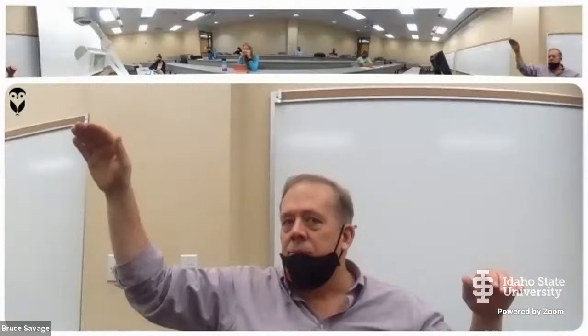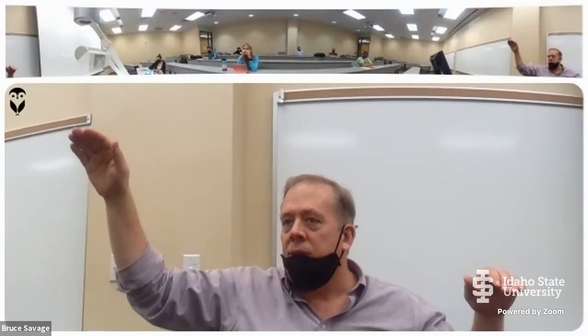So the question to the whole class, what happens if you have 100 feet of head and he puts in a pump that is designed to add 100 feet of head? That's the shutoff head. What happens then? Yeah, you may have a drop come out, or a drop go the other direction, but nothing. As soon as he puts in a pump with 101, then you're going to get a little trickle. And if you turn your rotational speed down on a variable speed pump, you can turn it so low that it's just not producing any flow whatsoever.